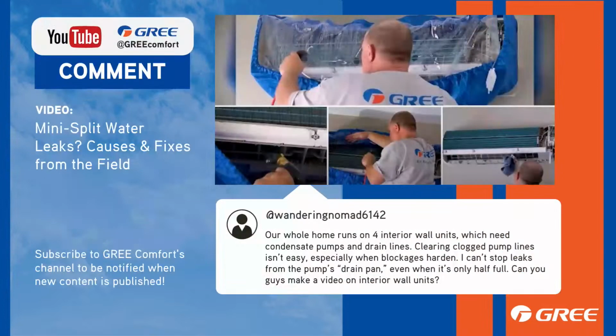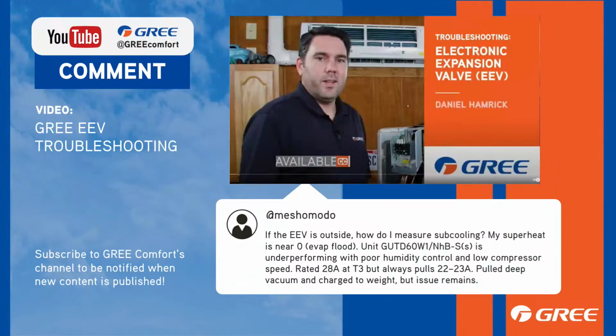So the GREE EEV troubleshooting video, we have a person that says, got a beautiful picture of Daniel here on this video. Thanks, Daniel, for that video. We have, if the EEV is outside, how do I measure subcooling? My superheat is near zero. Evap flood or flooded evaporator for superheat is down near zero.